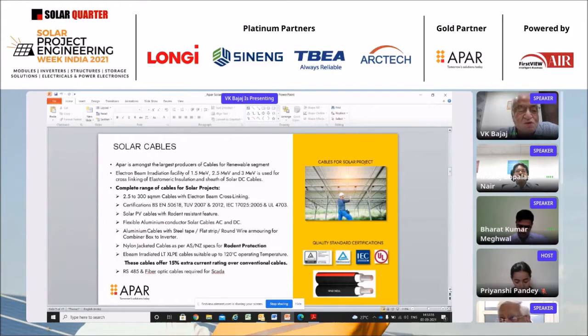We can also offer electron beam irradiated LT XLPE cables, suitable up to 120 degrees C operating temperature. These cables can offer 15% extra current rating over conventional cables. Of course, you have to consider the voltage drop and other aspects. But the cables can give you far more life than what is normally available from conventional cables.